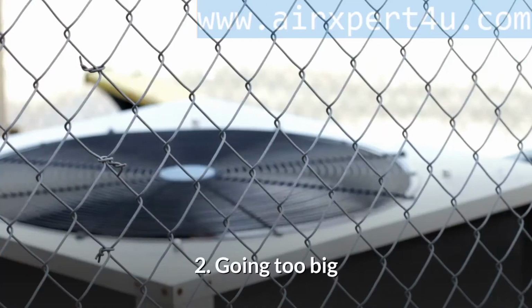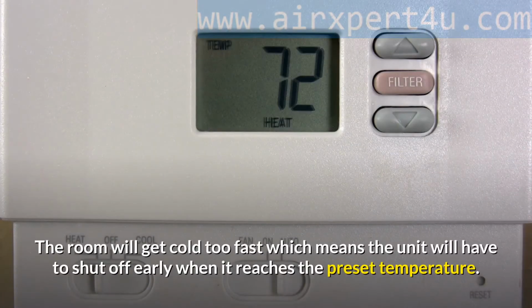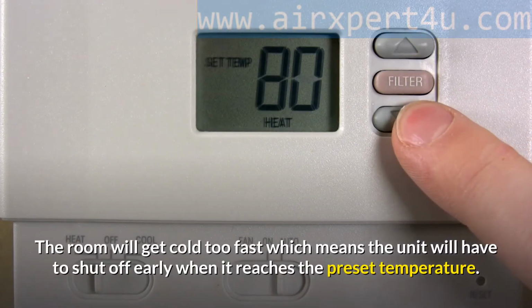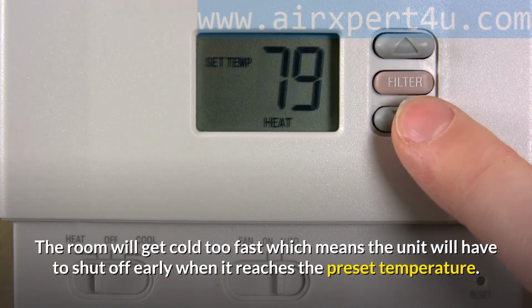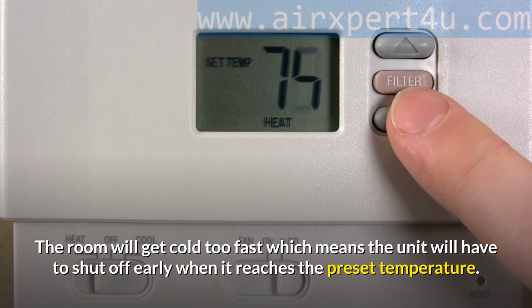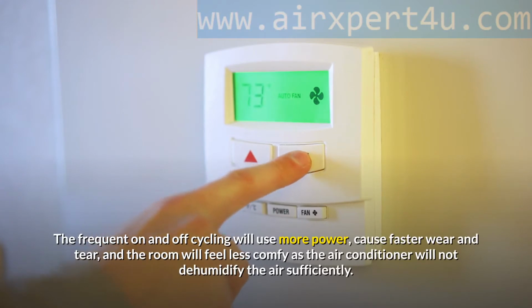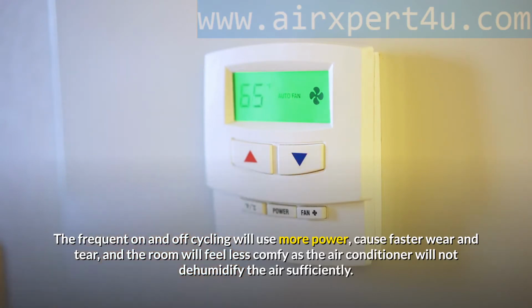2. Going too big. The room will get cold too fast, which means the unit will have to shut off early when it reaches the preset temperature. The frequent on and off cycling will use more power, cause faster wear and tear, and the room will feel less comfy as the air conditioner will not dehumidify the air sufficiently.